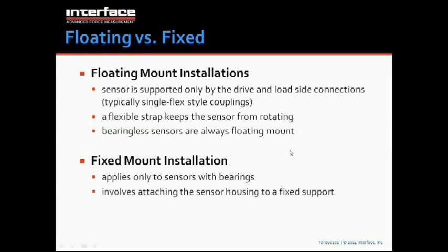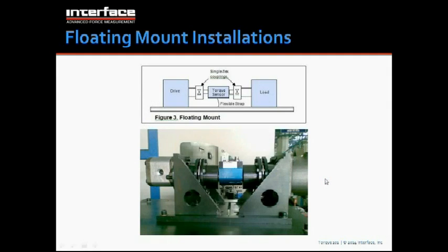Now, a fixed mount installation really only applies to sensors that have bearings, and that is when you actually take the housing of the sensor and mount it to a fixed support, and that takes a different type of coupling than a floating mount. With a fixed mount, you have alignment between each sensor shaft and the item that it's being attached to. This is an example of a floating mount installation.